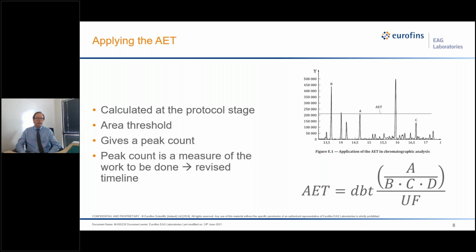Certain devices we can look at and we know it's probably not going to be a large peak count. A great example of this would be, again, those stainless steel surgical devices, right? Very high AET, very little extracting off. We're going to be in the clear, almost certainly. On the other hand, we can look at a device, something very large and complicated or made of an unusual material, and you may have data already that there may be degradation issues or some other aspect of it that's going to make for a very complicated extractables profile, and we can predict ahead of time that yes, it may take longer. So those conversations are important, but again, peak count here tells us what's left to be done.